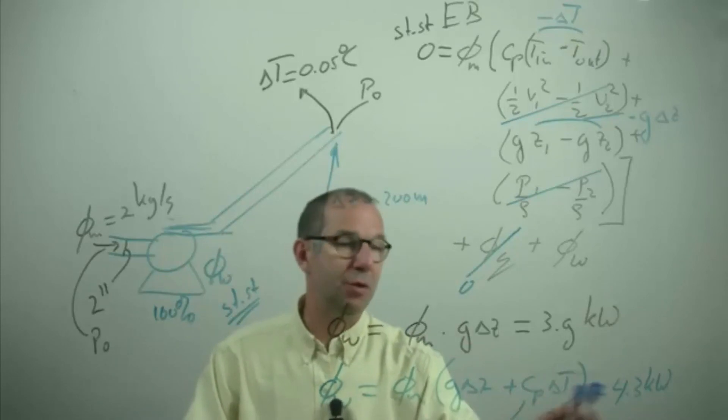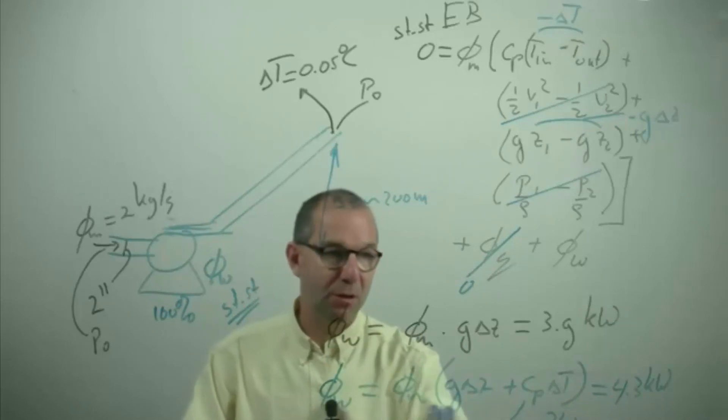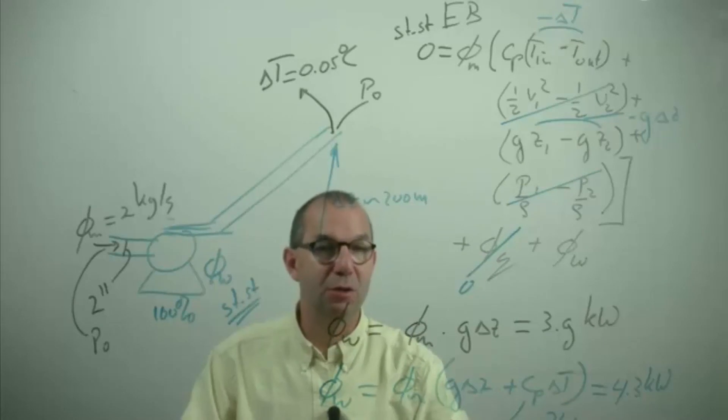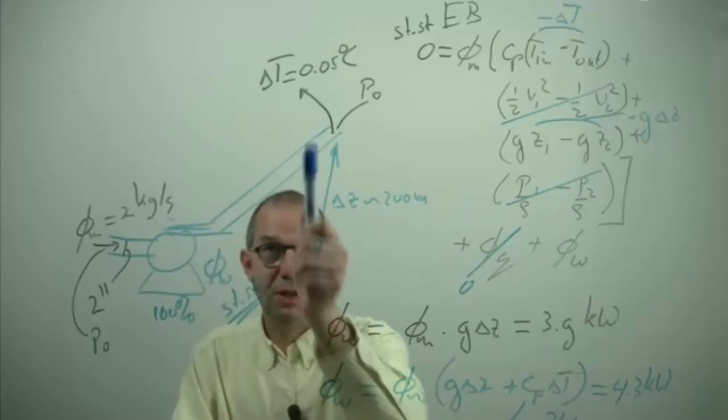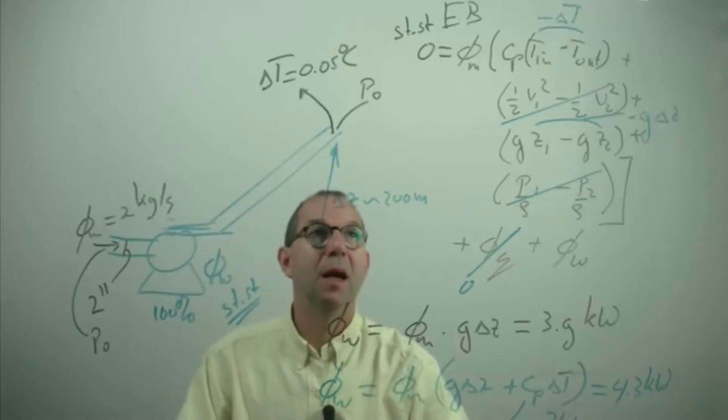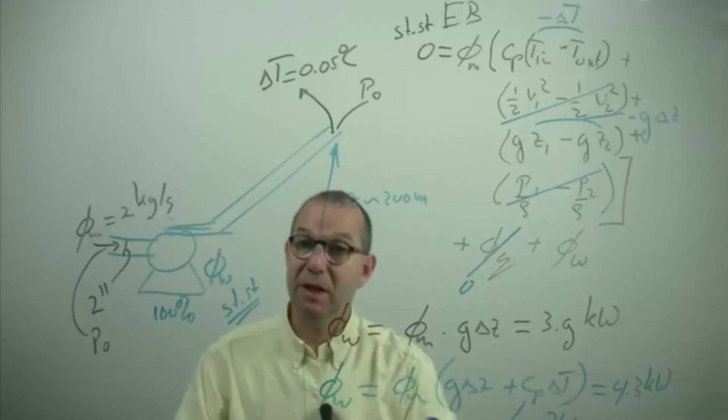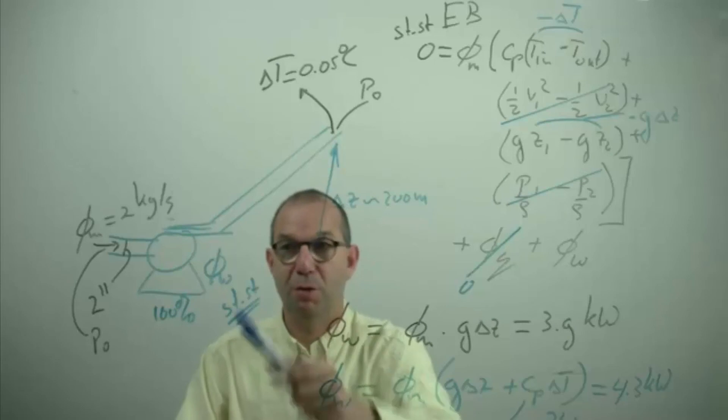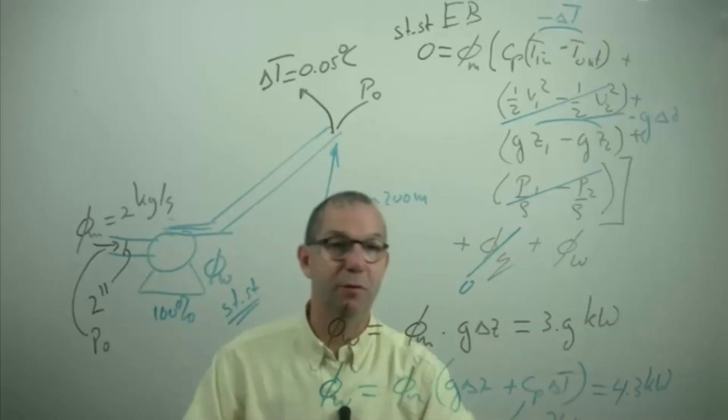Ok 10% is that much or is that little, well it's not too bad but it's a loss term that is there. Moreover your pump will probably have to be a little bit stronger, it needs to supply a little bit more power as we assume that everything that a pump generates is turned into energy that is useful in this equation. In practice it's not, the pump will heat up itself and there is a loss term, so the efficiency of the pump is less than 100% and you need a heavier pump.